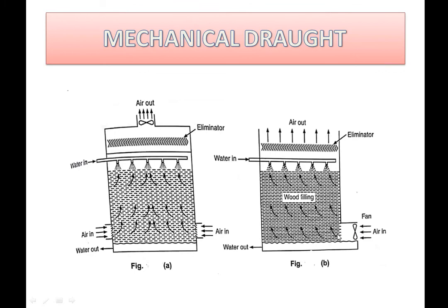In the forced type, the fan is present at the air inlet. The air passes through the wood filling and is blown out from the top of the tower, and the cold water is collected from the bottom. The key difference is the placement of the fan: at the top in the induced type and at the bottom in the forced type.